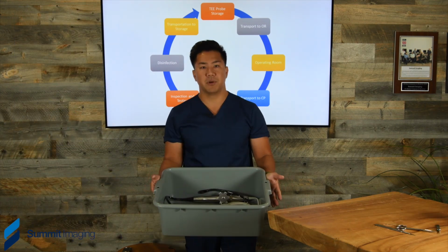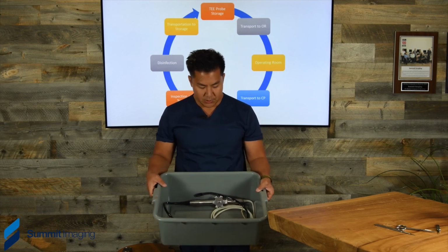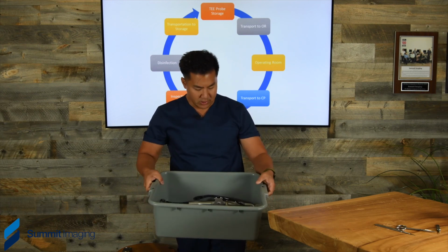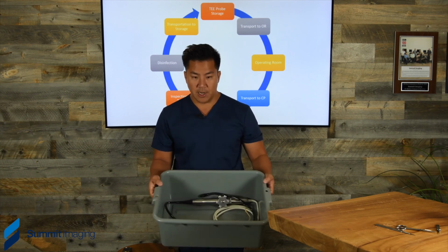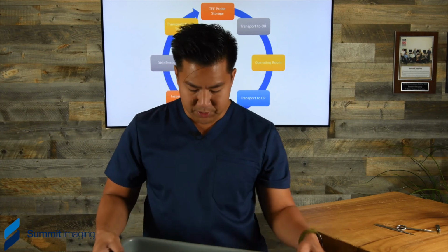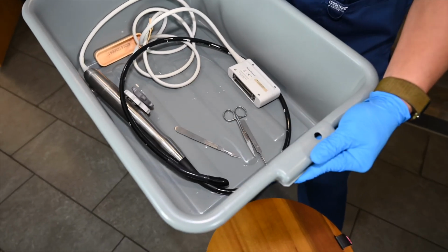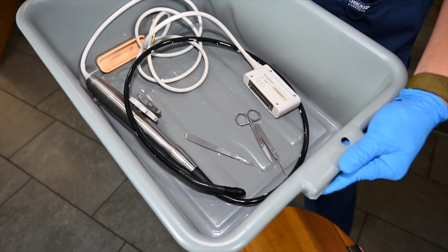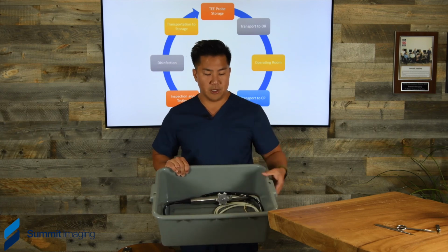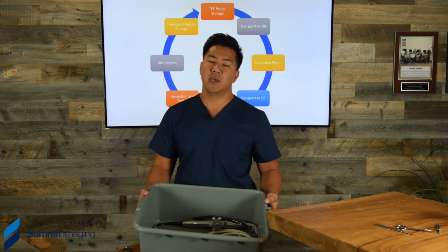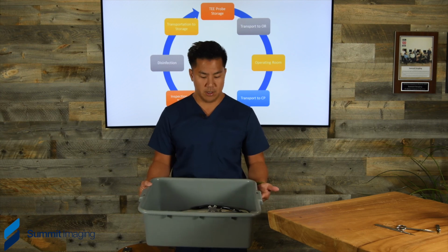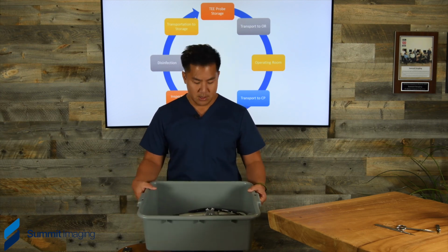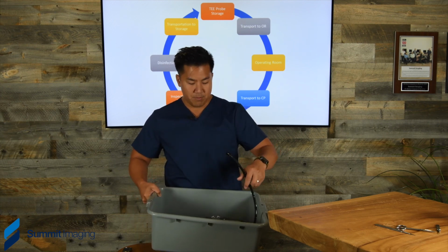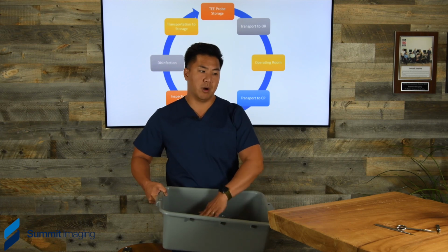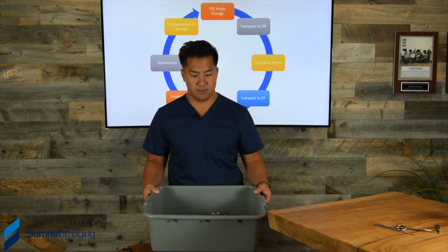And now we have a similar tote for a TEE probe. And as you can see, same rules apply, but you've got another variable, this really heavy handle. And as you're walking around, in this particular case, this will be banging against the handle, the metal piece. It'll hit as you're walking around and shimmying this around on accident just by natural walking motion. So we really recommend that we just keep the tip away from the metal parts and prevent impact.